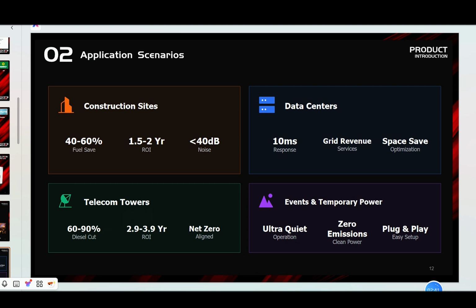Now I will introduce 4 points. First, construction sites. This is the scenario most closely related to your existing business. The hybrid system, battery plus diesel systems, reduces diesel use by 40 to 60%, with payback in 1.5 to 2 years. Operating noise is below 40 dB. They can work on urban sites and night shifts without noise cancelling. They also optimize genset operating conditions, extending equipment life and reducing major overhauls.